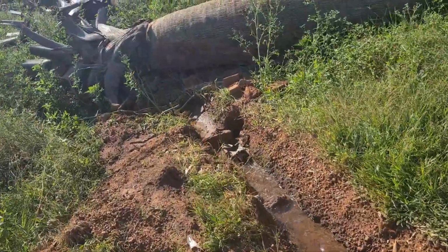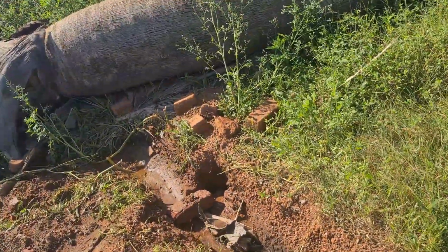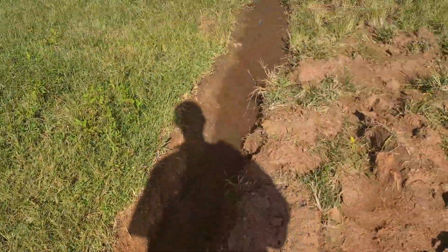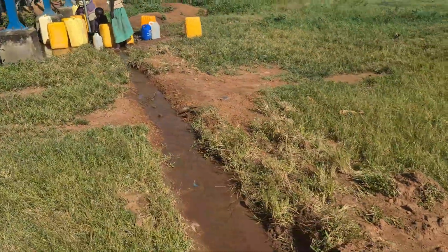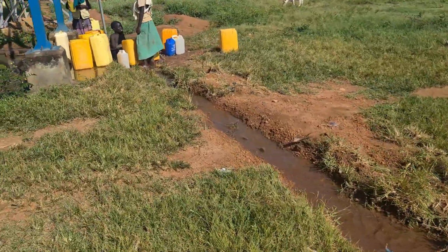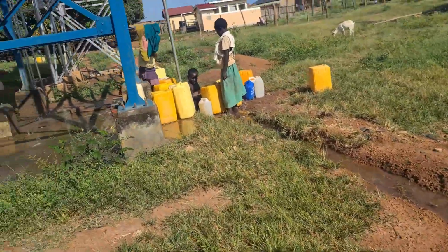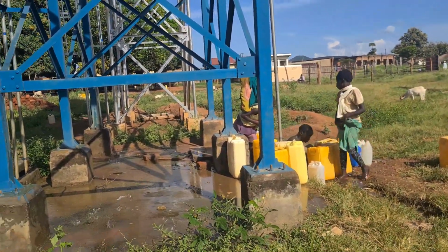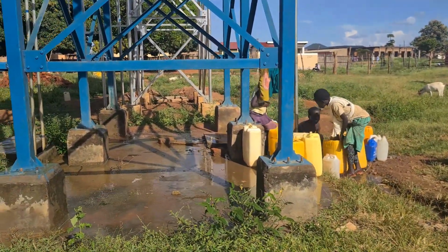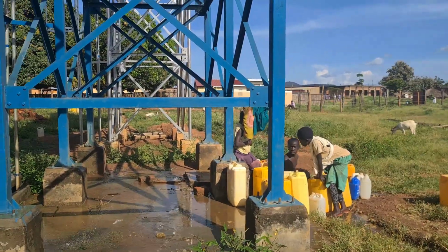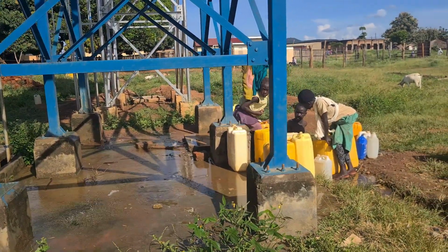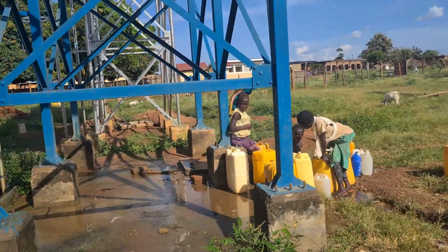disadvantages is that you reduce the pumping system service life, because the pump continues to pump even if there is no need. So you reduce the service life for the pump, and it will mean that every day it will be pumping and the tanks will be full.